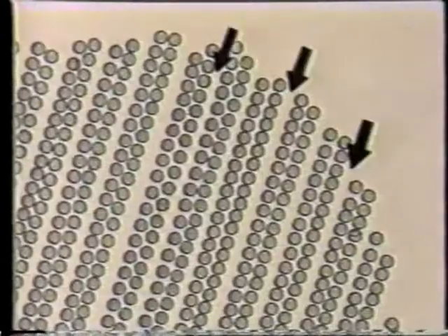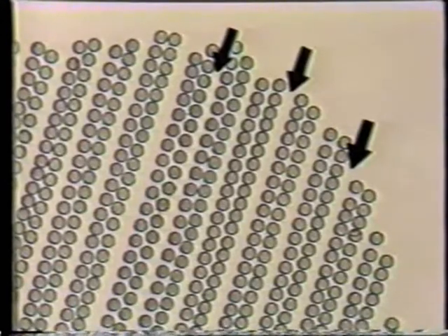These lower tubes are often referred to as the vent condenser. Like the tubes in the air exit lanes of a single-pass condenser, these tubes condense the steam in the steam-air mixture flowing through the air exit lane. Between the two halves is a central steam lane. There are side steam lanes around the outside of the tubes. As we look at a section of the tubes close up, you'll notice that there are also steam inlet lanes between these tubes. That's basically the similarities between the single-pass and two-pass condenser design.